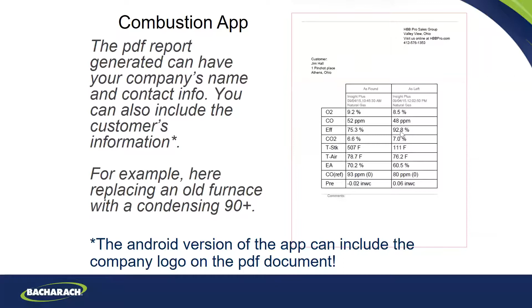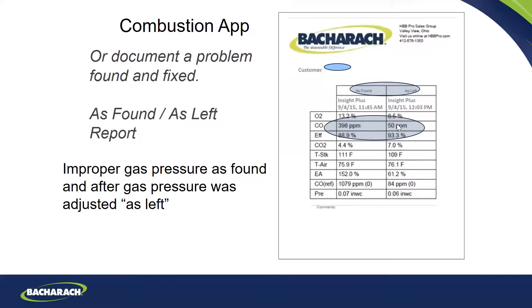Okay, here's another one where we have as found, as left, and it was improper gas pressure. So the problem here was the high CO. Okay, and so it was either overfire or underfire. They corrected the CO, the CO went down to 50, and so it did change the efficiency pretty drastically. But when you corrected that gas pressure, it lowered the oxygen automatically. But it definitely lowered the carbon monoxide.